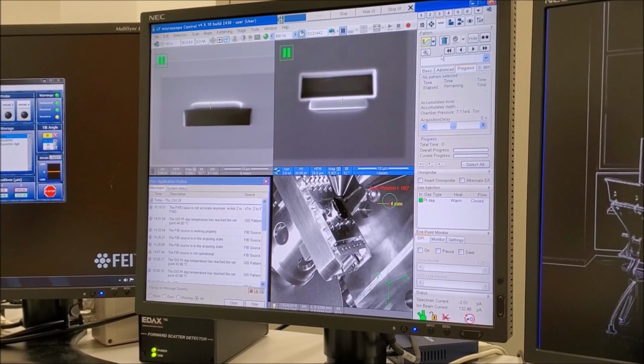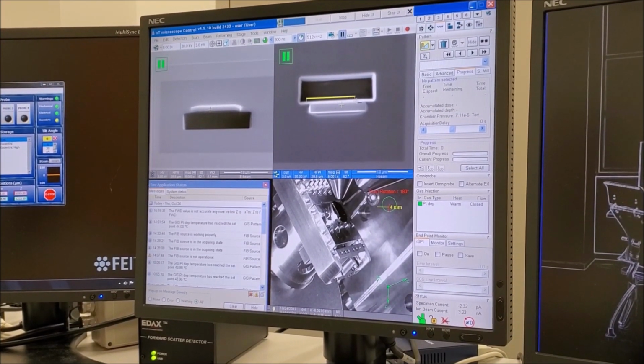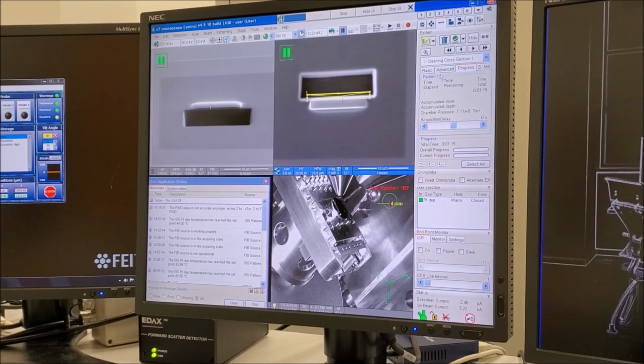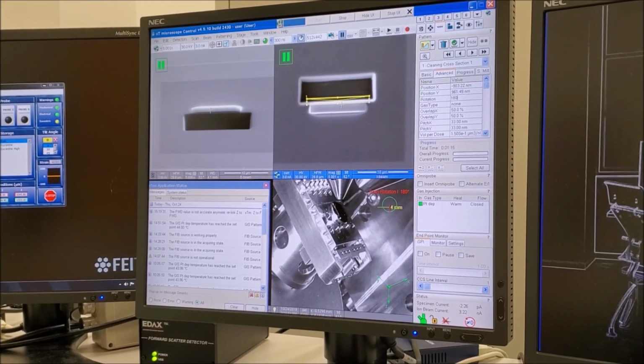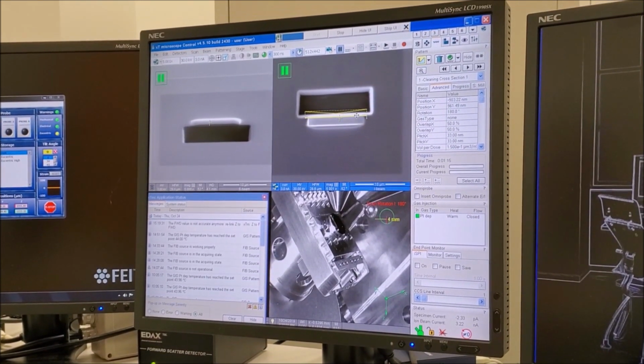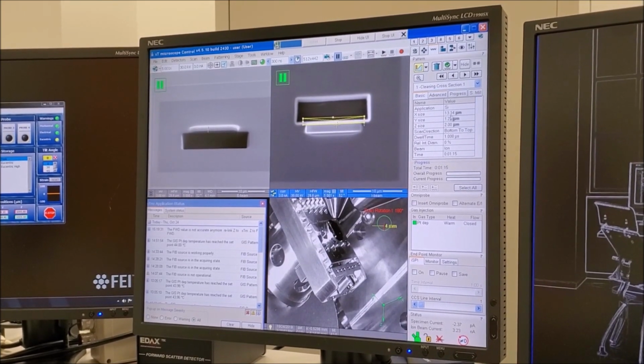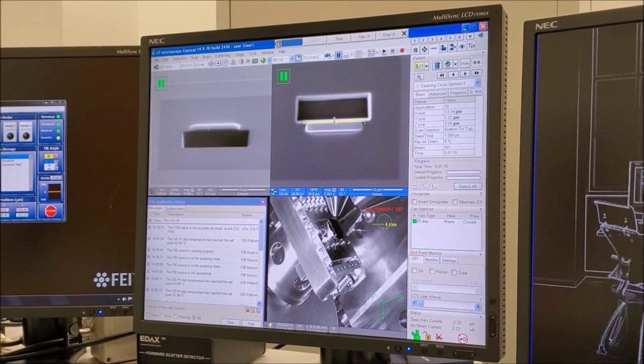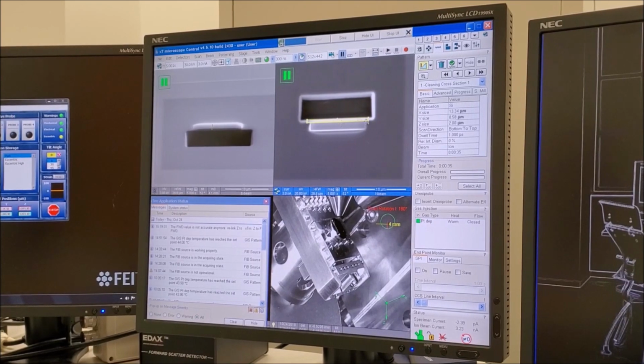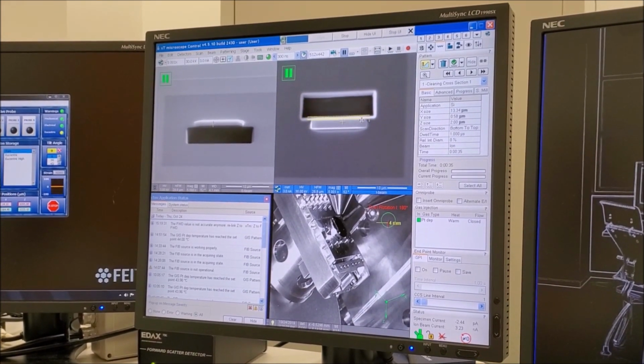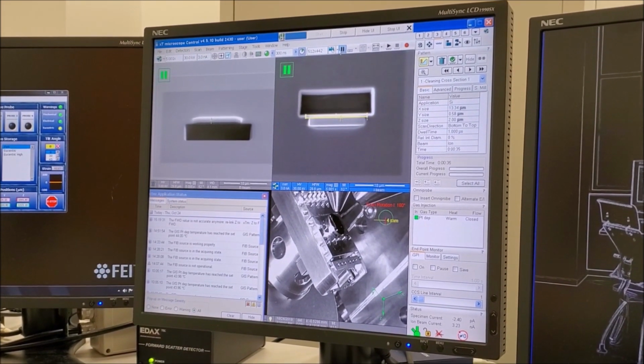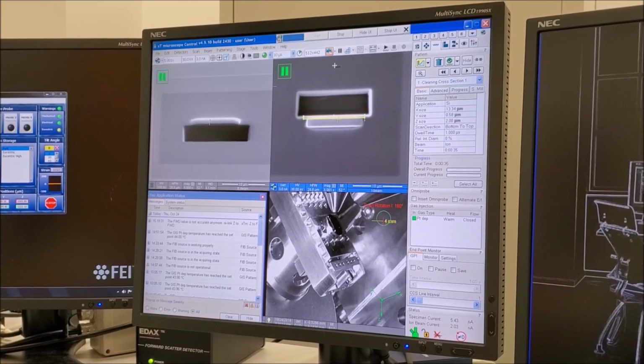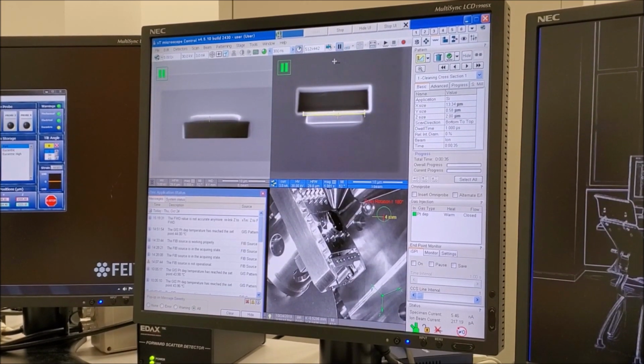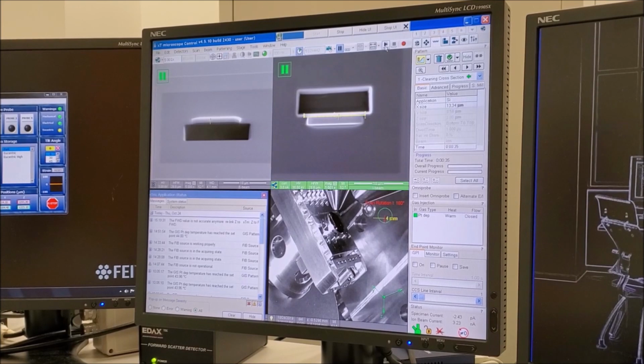In the patterning module, select the cleaning cross-section and then click and drag on the image. In the Advanced tab, adjust the rotation so the thick line of the pattern is closest to the platinum strip. Then return to the Basic tab, make sure that silicon is selected under Application, and adjust the X, Y, and Z parameters as needed. Acquire one more snapshot, and then click and drag and position the pattern as needed.